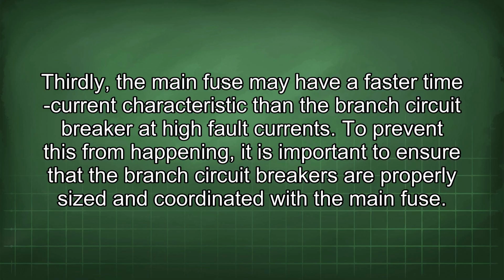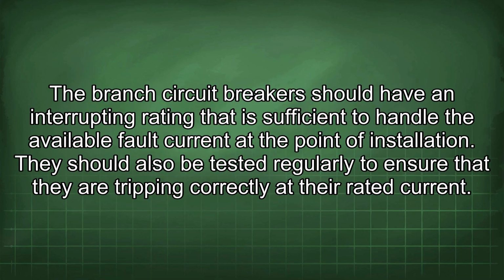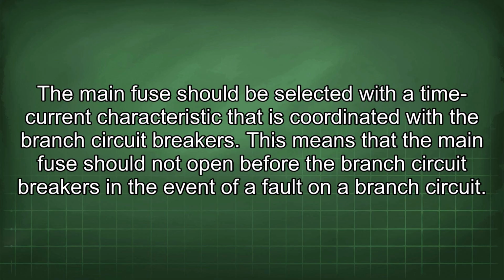To prevent this from happening, it is important to ensure that the branch circuit breakers are properly sized and coordinated with the main fuse. The branch circuit breakers should have an interrupting rating that is sufficient to handle the available fault current at the point of installation. They should also be tested regularly to ensure that they are tripping correctly at their rated current. The main fuse should be selected with a time current characteristic that is coordinated with the branch circuit breakers. This means that the main fuse should not open before the branch circuit breakers in the event of a fault on a branch circuit.